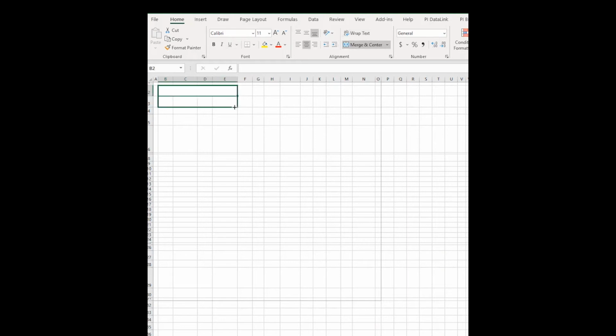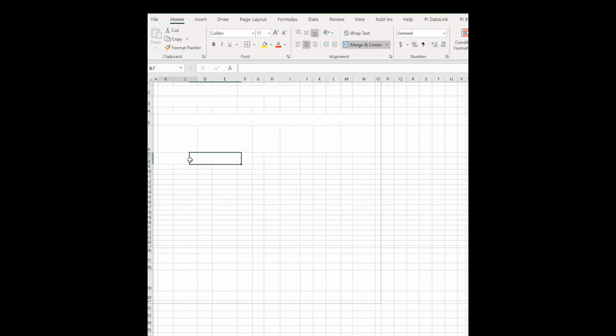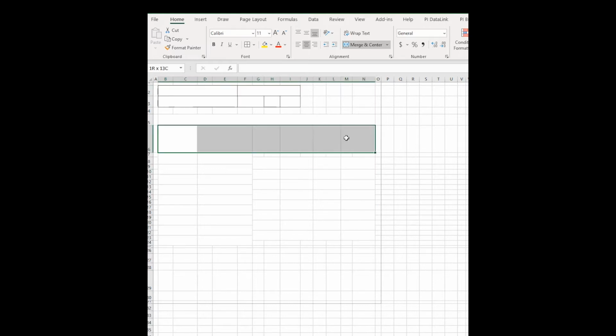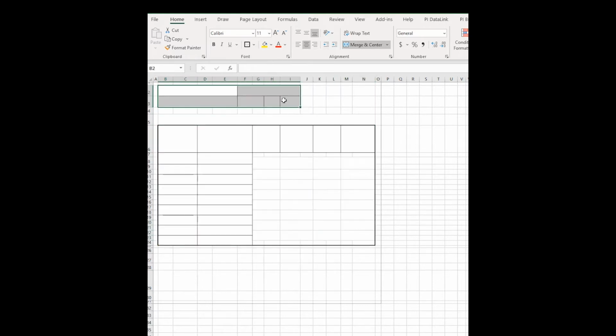This video is going to provide a step-by-step instruction on how to build your own auto-calculating form for testing proximity probes, specifically the proximity probes used in equipment monitoring applications. These probes are used to measure relative vibration, axial thrust, and equipment rotation.